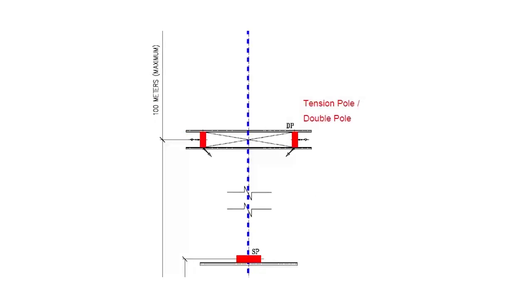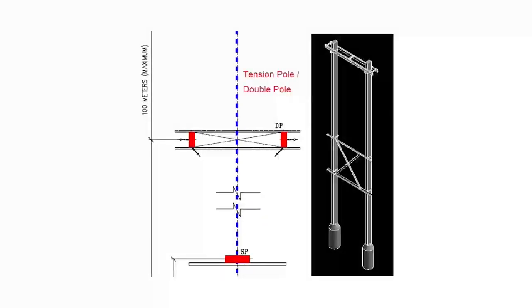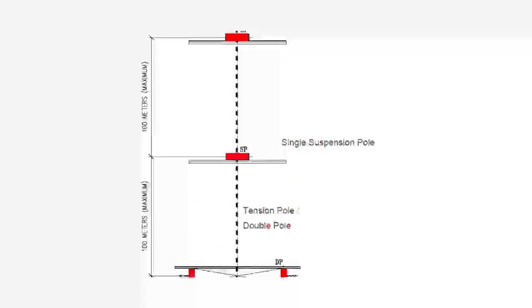At every 1 kilometer, we are supposed to break the line where we introduce one double pole structure as indicated in the isometric view which has been shown, wherein we cut the line and then provide a jumper to continue the line. There is no need to say that required stays are to be provided as per the requirement. So, the line goes, there is a double pole at 1 kilometer, and then further the line continues. This photograph indicates the line which has been drawn, which is going straight with maximum span, single simple pole and a double pole cut point.